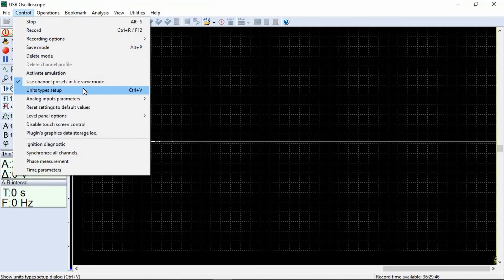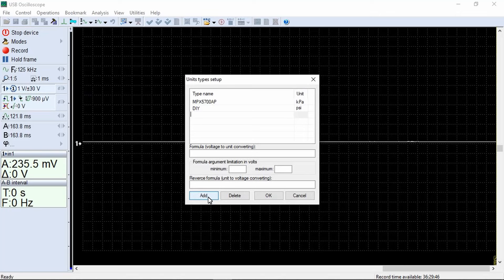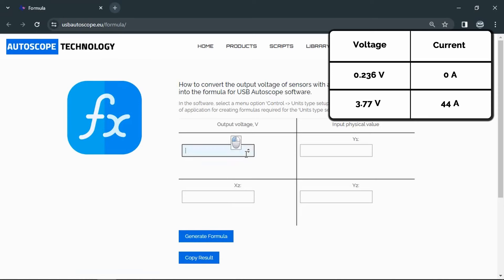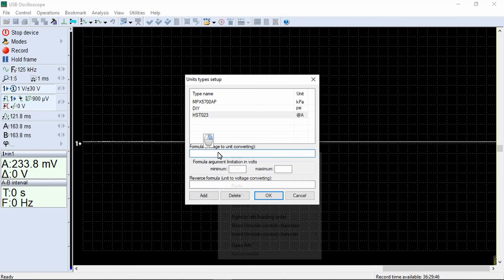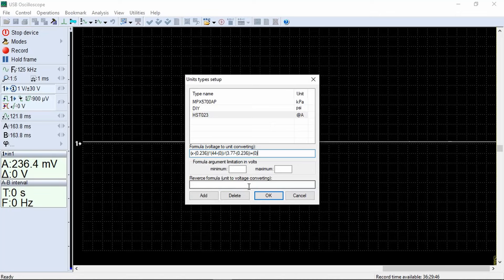We create a transducer named HST023 with the unit of measurement amperes. The SI prefix before the unit of measurement is replaced in the display with prefixes nano, micro, milli, kilo, or mega. If the SI prefix is not specified, values are displayed without a prefix. We generate the formula and copy the result. The argument limitation group is optional and defines the range of permissible values for the output signal voltage. If the signal voltage exceeds this range, the calculation is ignored and an ellipsis is displayed. For our transducer, we enter a minimum of minus 4 volts and a maximum of 4 volts. We press OK and save the setting, then check the operation.